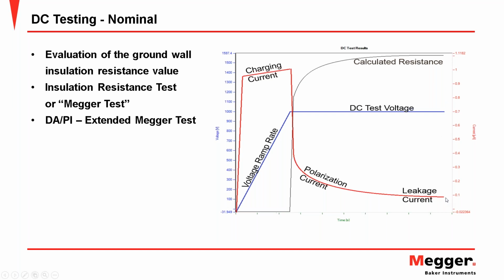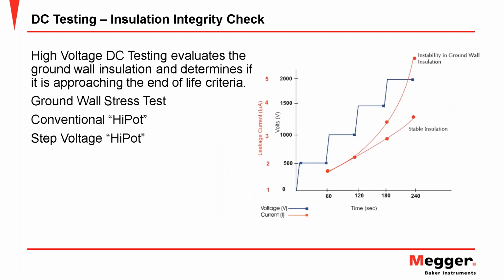And then at the end of 1 minute, we'll take that final leakage current and we'll take the voltage divided by that final leakage current, and that will give us the calculated resistance. So over time, if you're used to looking at a MEGGER meter and we see resistance increasing over time, that's this black line that we see here, increasing over time. But what's really happening is we're holding voltage constant and we're dividing that voltage value by this decaying current, which results in that calculated resistance. So it is important to keep in mind that resistance is a calculated value, not a measured value. So again, this isn't intended to be stressful. It's just, again, at the nominal voltage of the motor, we're trying to quantify that resistance for comparison purposes.